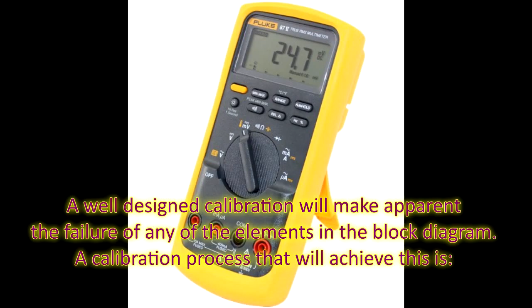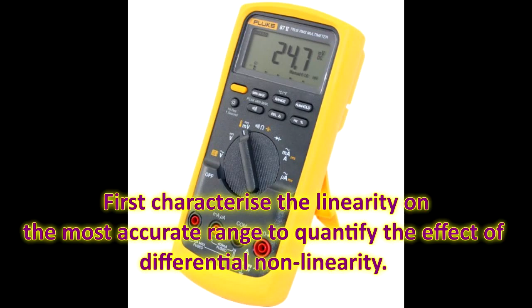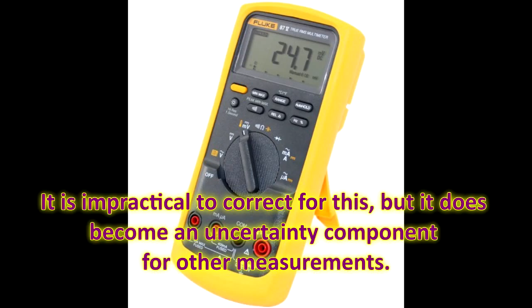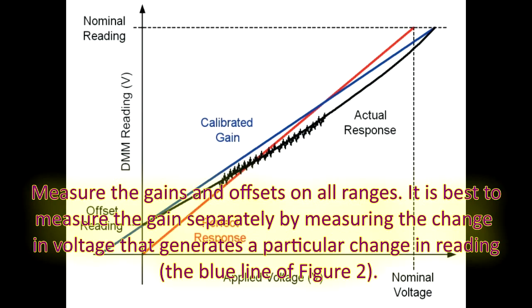A calibration process that will achieve this is: first, characterize the linearity on the most accurate range to quantify the effect of differential nonlinearity. It is impractical to correct for this, but it does become an uncertainty component for other measurements. Measure the gains and offsets on all ranges. It is best to measure the gains separately by measuring the change in voltage that generates a particular change in reading, the blue line of Figure 2.